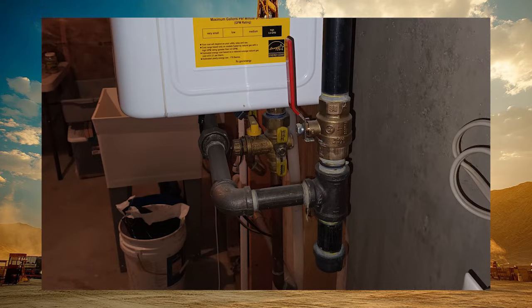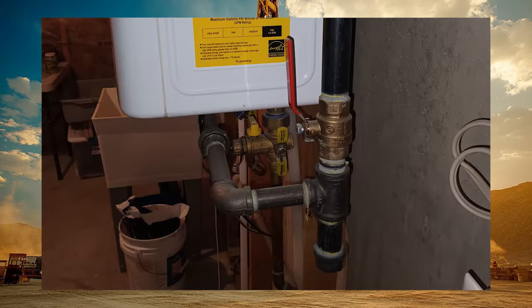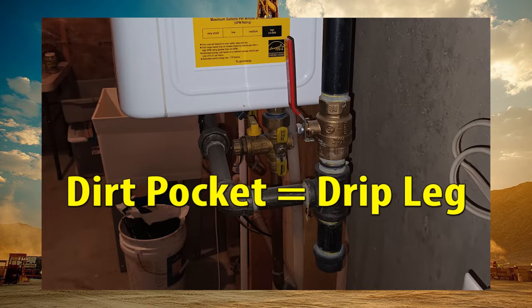Now that is very accurate, but when we're actually talking about gas, it's a sediment trap for debris and oil in the gas line. The most common forms of debris inside a gas line are going to be the swarf, or metal shavings from threading pipe, and the oil from threading it as well. But other stuff can get trapped in there, especially during the construction phase. A name that is commonly used for the dirt pocket in the field is a drip leg.